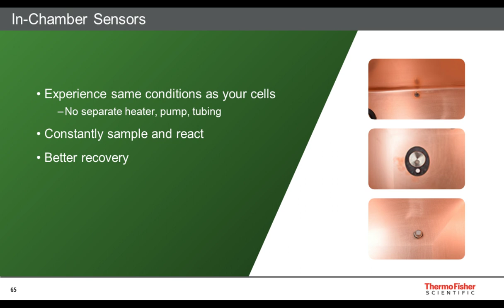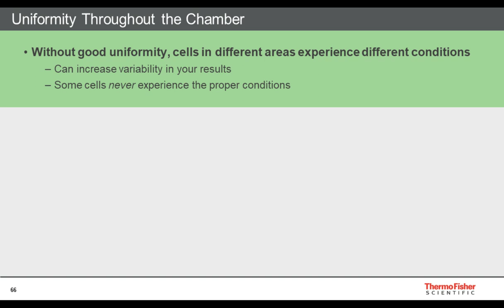Now I just want to finish up by talking about uniformity. Another thing to think about with regard to an incubator for cell therapy, especially as you're getting to larger incubators and larger culture vessels, is that you want the cells, regardless of where they are in the incubator, to experience the same conditions, because cells react to changes in temperature and pH and the concentration of nutrients in the medium. So you want the incubator to give you the same conditions regardless of where you look in the incubator chamber. Uniformity throughout the chamber from top to bottom is important.